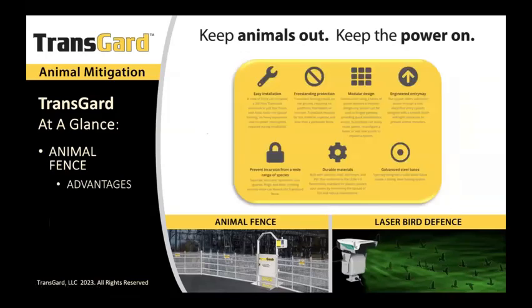The advantages of the fence are really easy installation. We don't have to take a shutdown to install this fence to protect the low side, the high side, or an entire substation. It's a freestanding protection with modular design. It can grow with the substation and be easily adapted to a new design or area of protection.